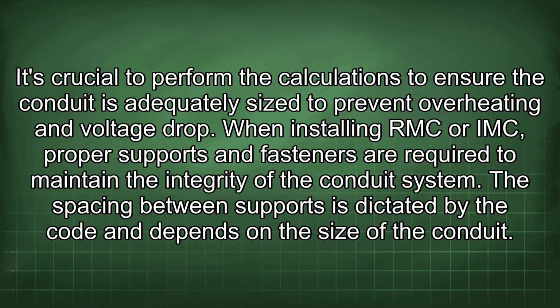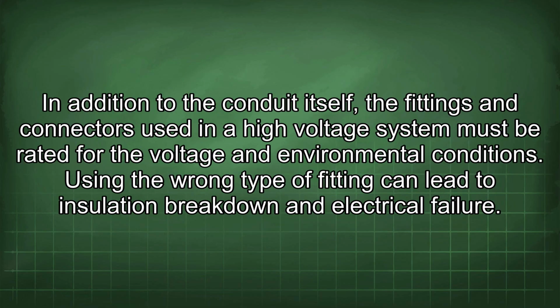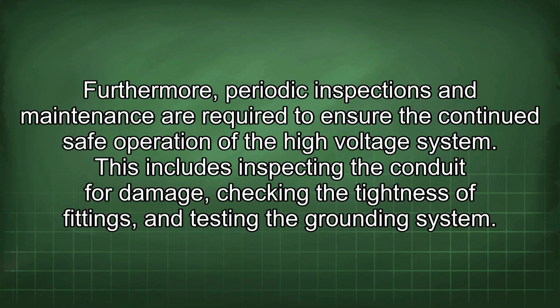When installing RMC or IMC, proper supports and fasteners are required to maintain the integrity of the conduit system. The spacing between supports is dictated by the code and depends on the size of the conduit. In addition to the conduit itself, the fittings and connectors used in a high-voltage system must be rated for the voltage and environmental conditions. Using the wrong type of fitting can lead to insulation breakdown and electrical failure. Furthermore, periodic inspections and maintenance are required to ensure the continued safe operation of the high-voltage system. This includes inspecting the conduit for damage, checking the tightness of fittings, and testing the grounding system.